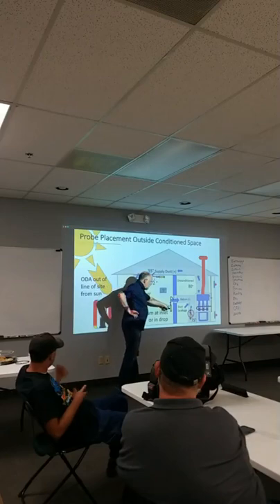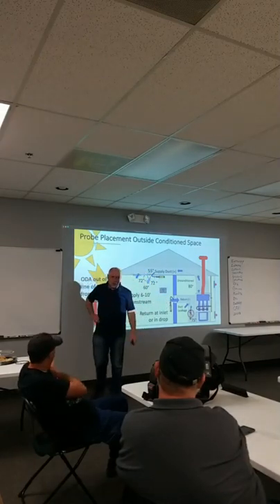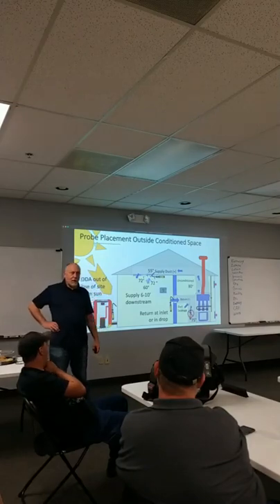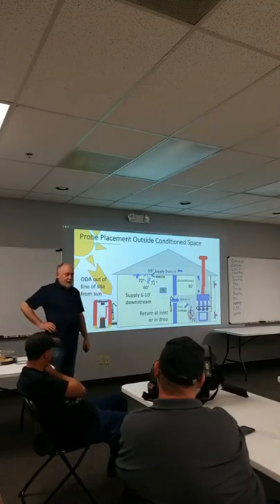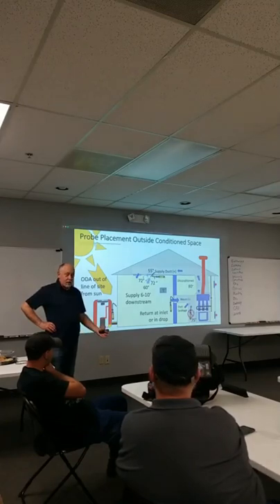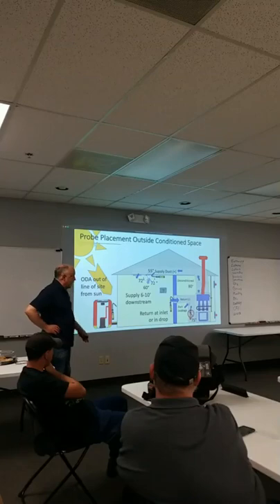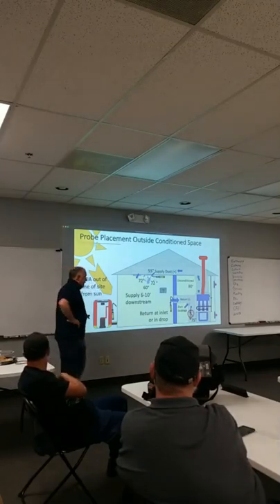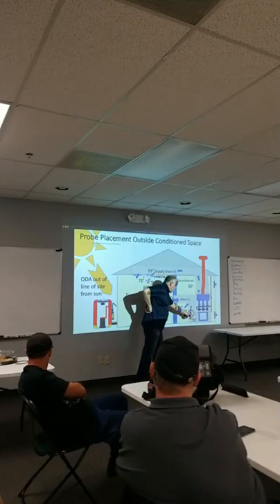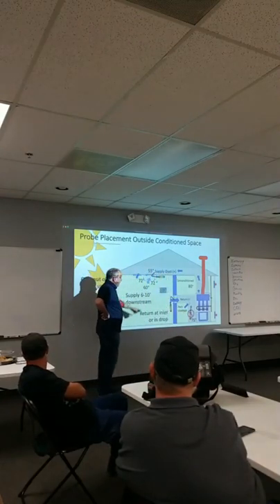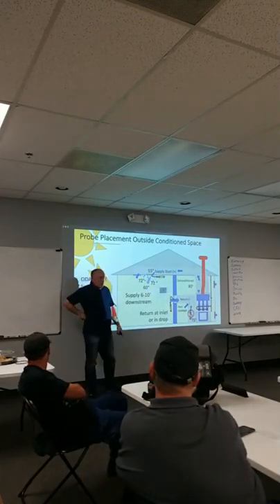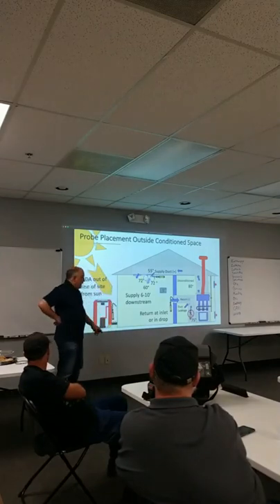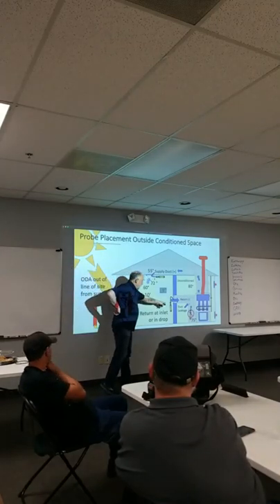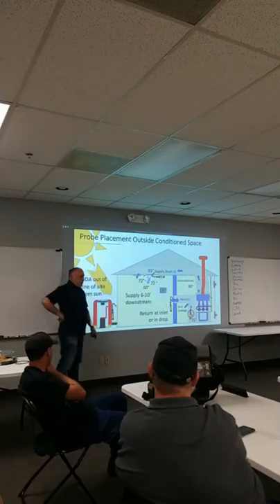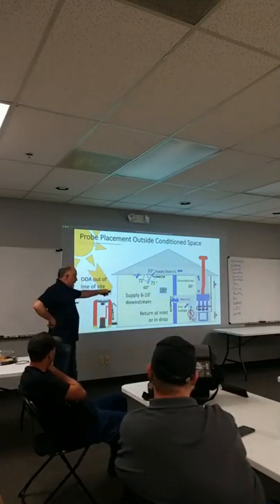When we're using Measurequick, we wanna test from inlet to outlet, especially in an unconditioned space. The software will pick up duct leakage. Yes, and you'll see this a lot, where it says, hey, you might have duct leakage on your system. That could be curb leakage on a rooftop unit, because the curb's not properly sealed. If we saw 75-degree air going in there, and we looked at 55-degree air coming out, we got a 20-degree split, probably working just fine. In reality, if it was 72 degrees in that room, we just eroded 3 degrees of temperature split. And the software will pick that kind of stuff up.